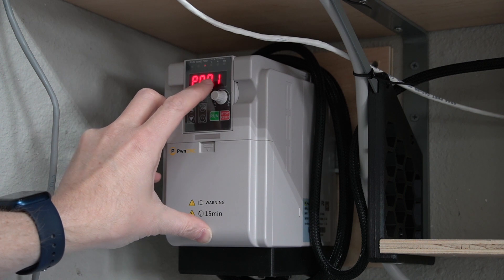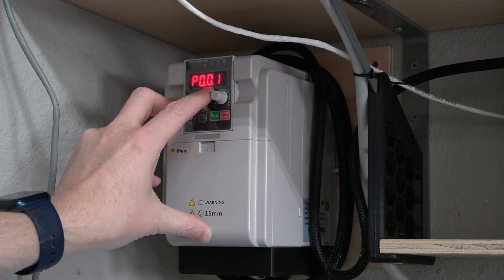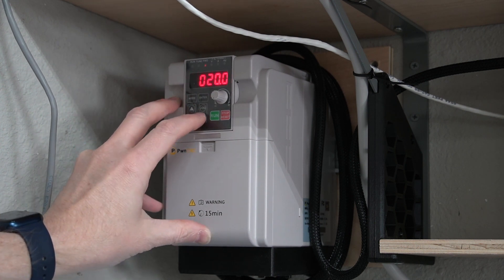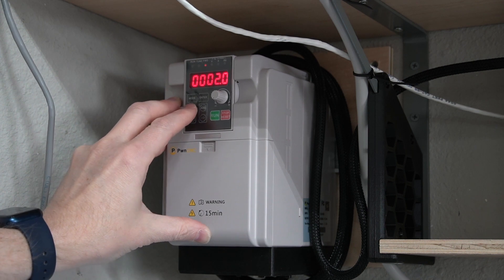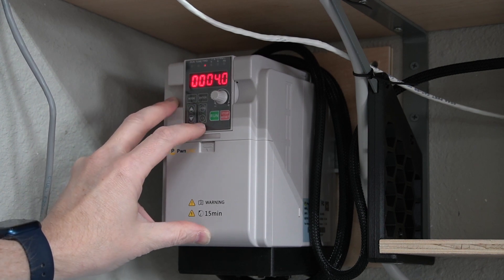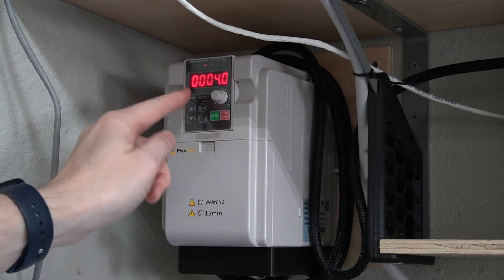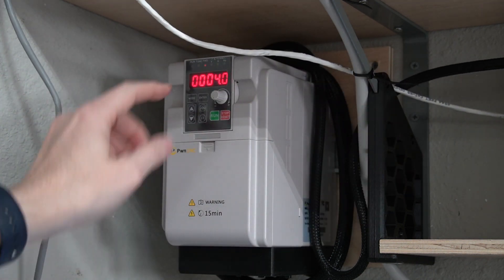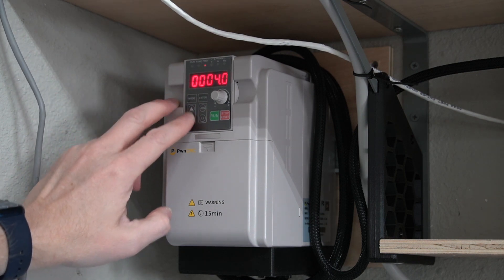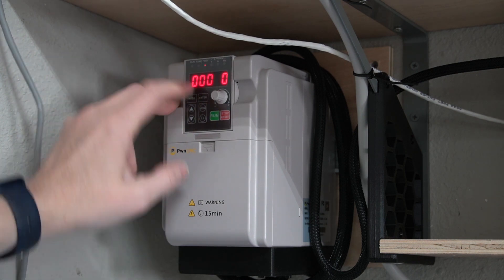We're also going to go to 12, so we want it to spin down fast as well so that we can change bits. We're going to change the P0.12, change that also to a four. You'll notice I'm using this right arrow which moves the cursor to the right and then circles back to the beginning, and then of course I'm going to use these up and down arrows to change the value, and then hit enter, and that accepts the value.